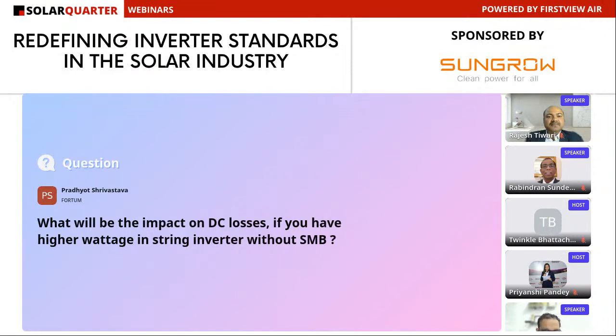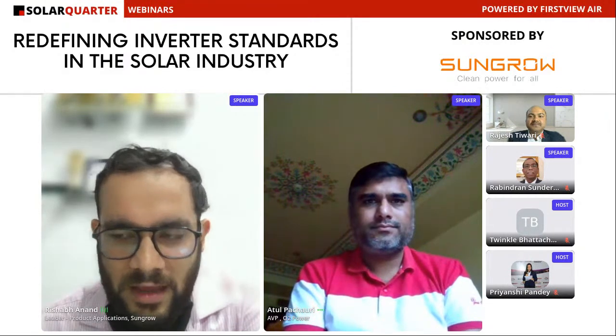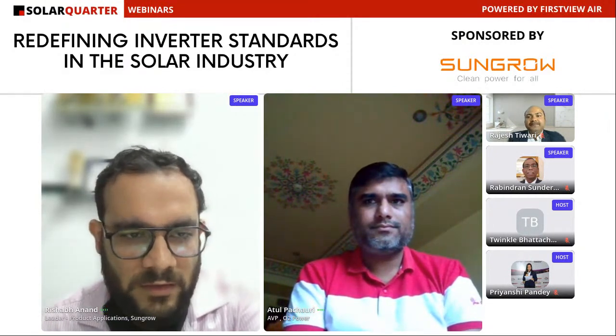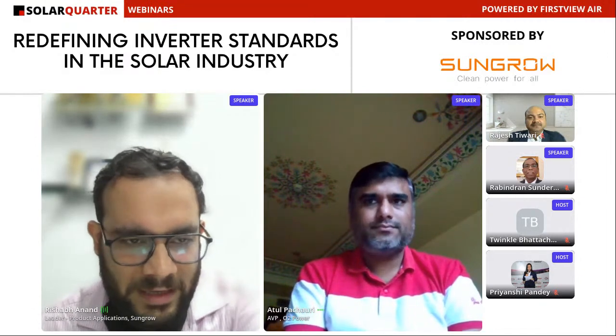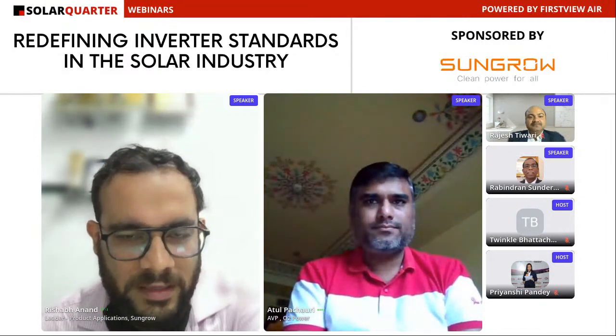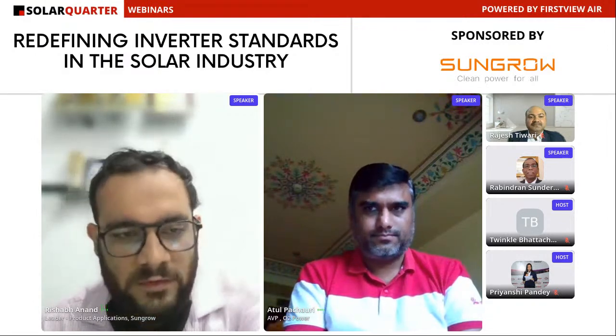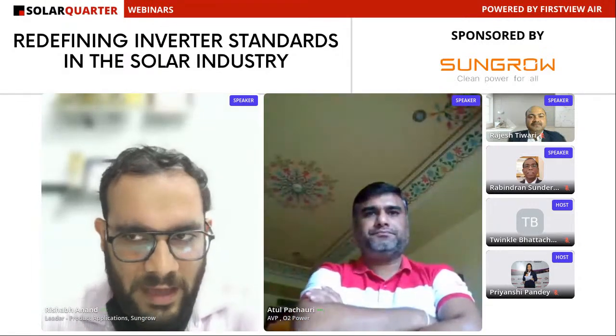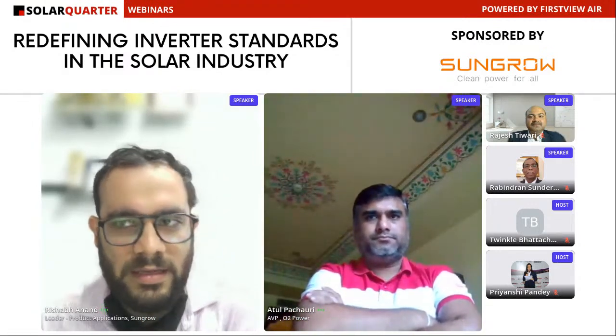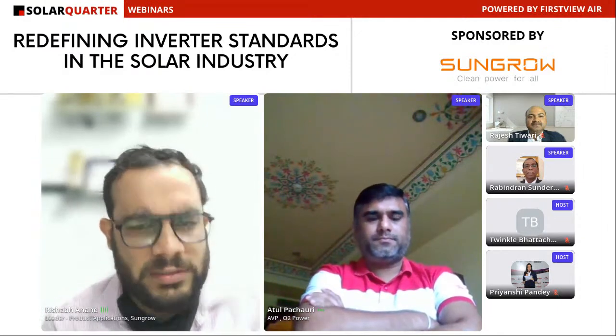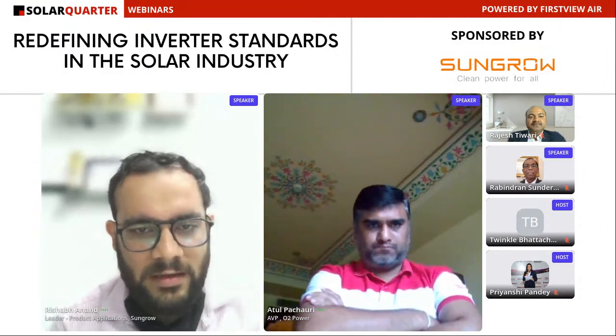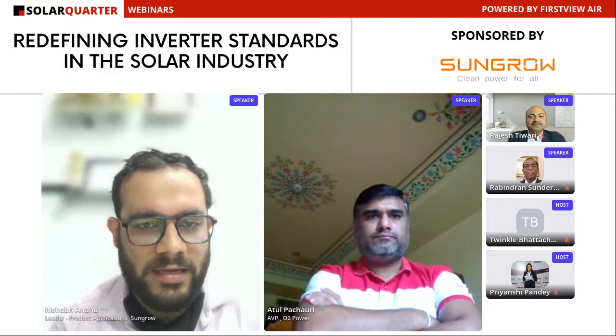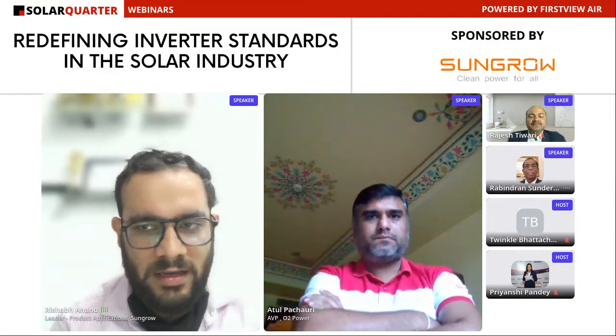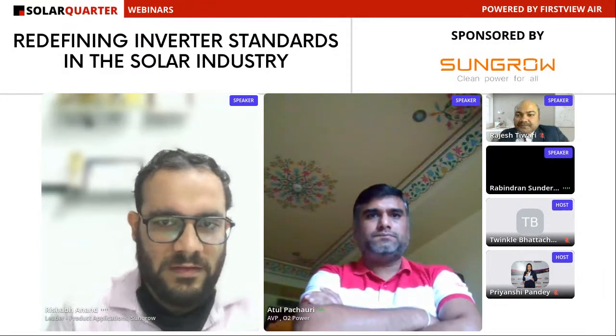Actually, a higher wattage in the string, and right now since you're having high wattage modules, they occupy considerably less land mass compared to the smaller watt peak rating inverters and modules. So that will have a reasonable amount of DC losses. Outside India as well, people are opting for up to 10 square mm solar cables, if required, to cover a larger area with a lesser amount of DC losses. So this is our observation, sir.